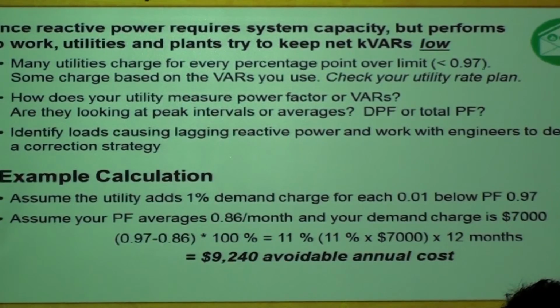Are they measuring? I think here you are just billed for kilowatt hours. They don't show you what your kilowatt or kVA is, what your reactive power is. They just bill you for kilowatt hours. And that's the thing, because consumers don't understand, if I have reactive power, that's wasted power, right? What's essentially happening is now I'm buying more power from the utility to compensate for that reactive power. So the utility is billing you for kilowatt hours, and as a consumer, you're just looking at kilowatt hours. But if you measure your reactive power, you know exactly how much is waste, so you can buy less.